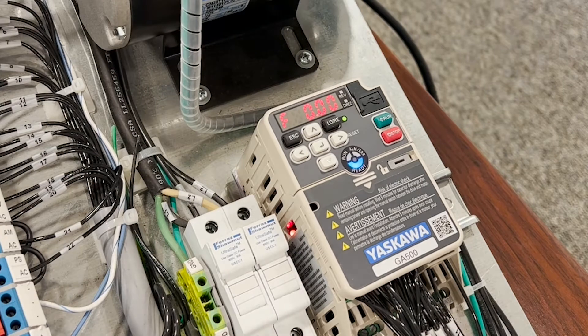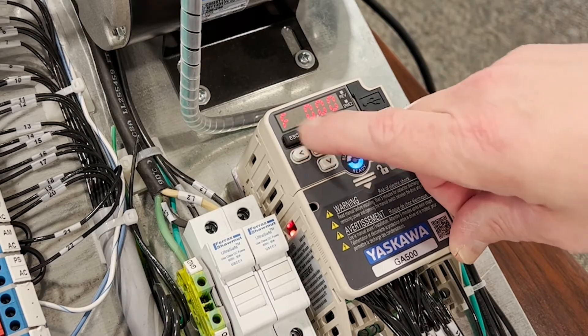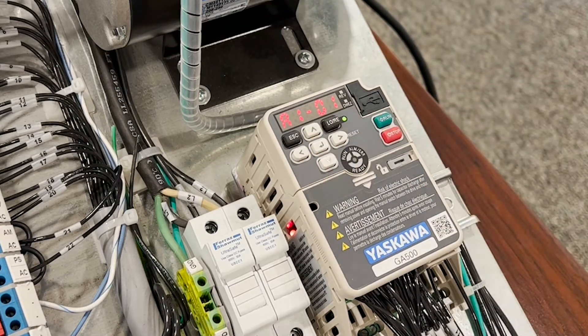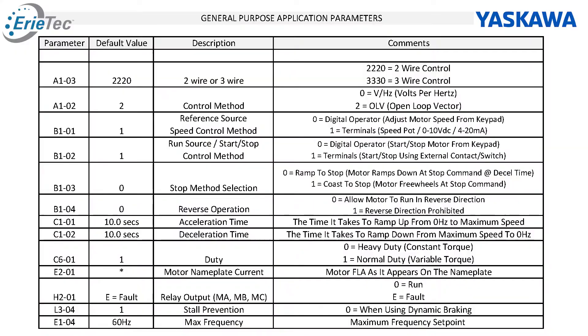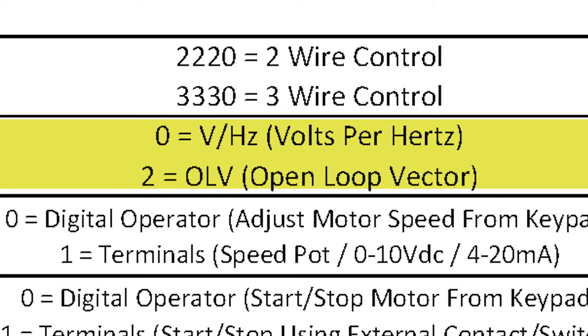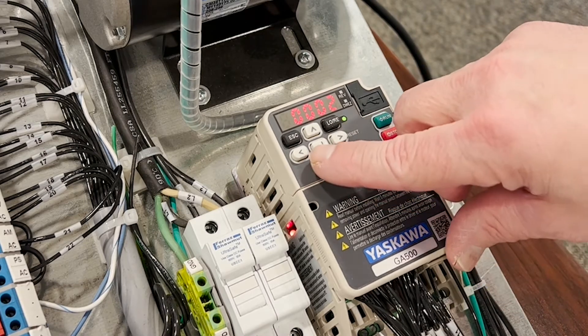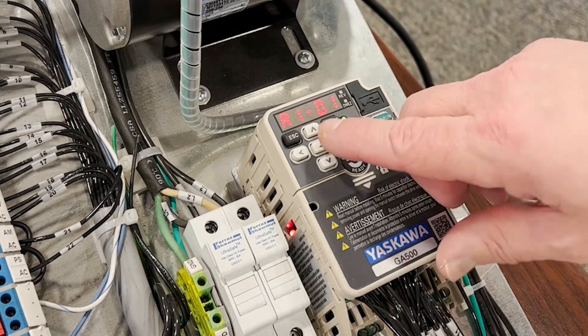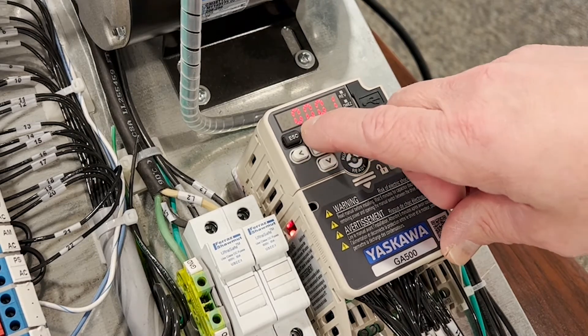To get started we need to determine our control method. On our application we're going to go into our parameters — PAR — and we're going to go to parameter A1-02. From the factory this drive comes defaulted at open loop vector. If we wanted to go to volts per hertz, we would change this to zero and hit enter. Once you see the end it means that it's taken the parameter and saved it.